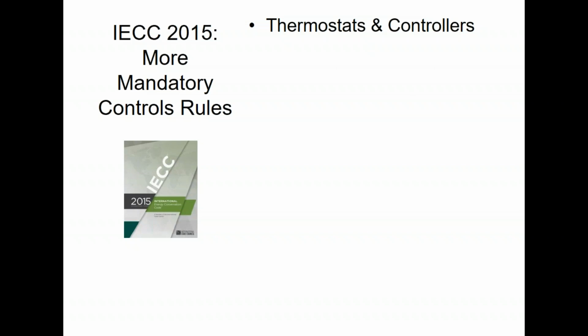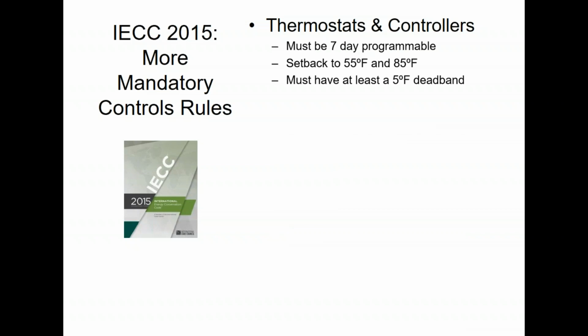Other mandatory rules in the IECC 2015. Before we get off the energy code and move to other codes, let's finish up this guy here. There are some key things for controls and then some very specific things for VAV, and then we'll move into the other codes. So thermostats and controllers must be 7-day programmable. That's not hard to do. Got to have setbacks initially set for 55 and 85. That's not hard to do. Personally, I like 60 and 80, but the code says 55 and 85.